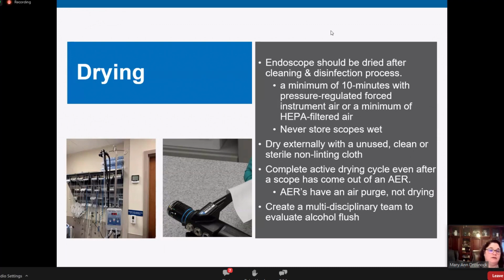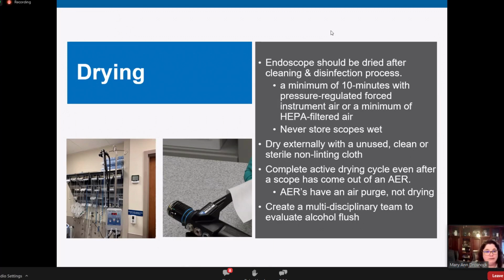And think about your alcohol flush. There are some guidelines out there that no longer recommend doing an alcohol flush. We know that some of the AERs have that automatically as part of the system, but what we recommend is a multidisciplinary team evaluate whether or not you still need to do that alcohol flush. Because if you're doing everything per the standards, guidelines, and IFUs, adding in all these quality parameters for cleaning verification, inspection, now drying, why would we still need to do the alcohol flush when we know it's not drying the endoscopes? We have a lot of evidence on that.